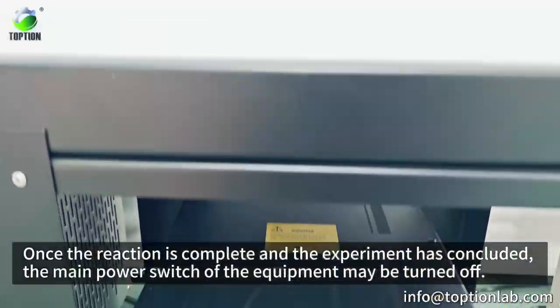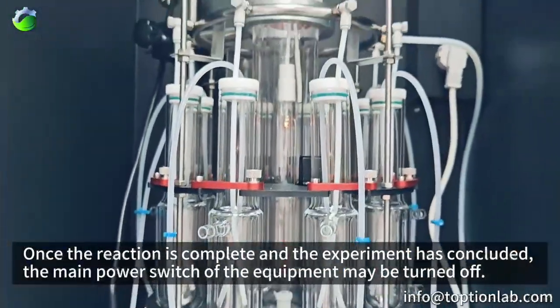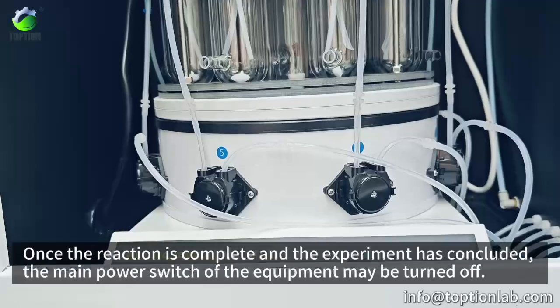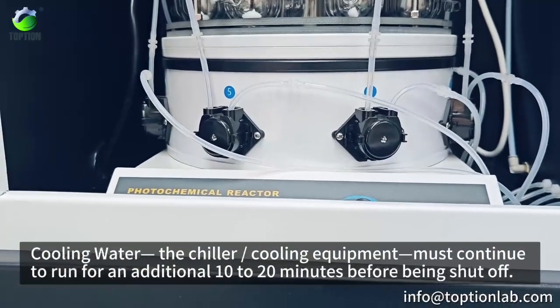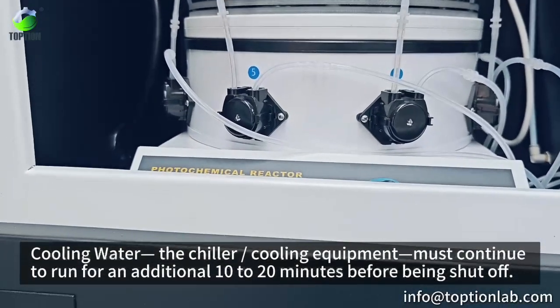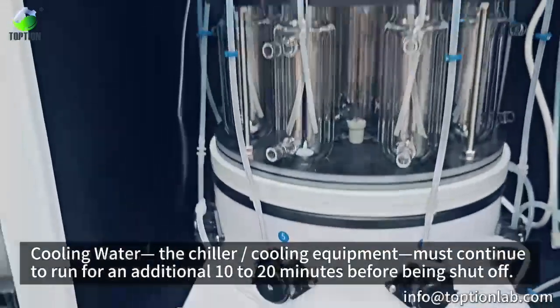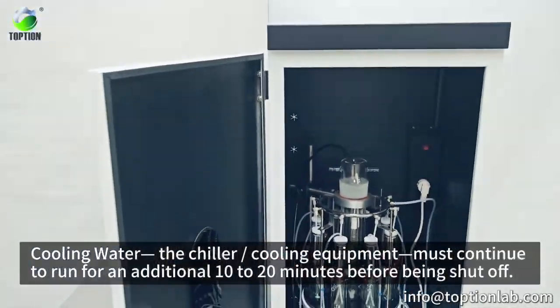Once the reaction is complete and the experiment has concluded, the main power switch of the equipment may be turned off. The chiller cooling equipment must continue to run for an additional 10 to 20 minutes before being shut off.